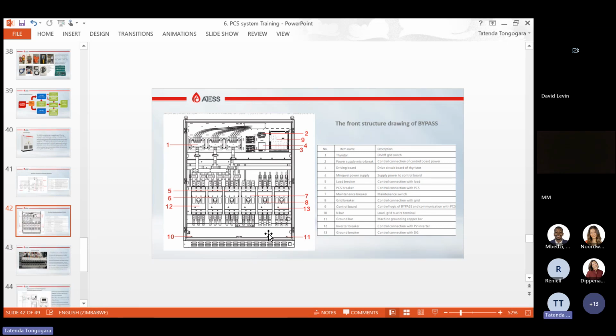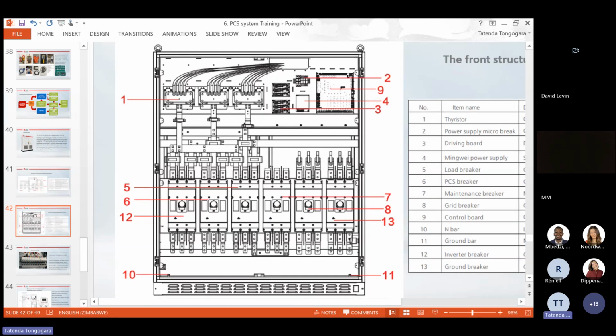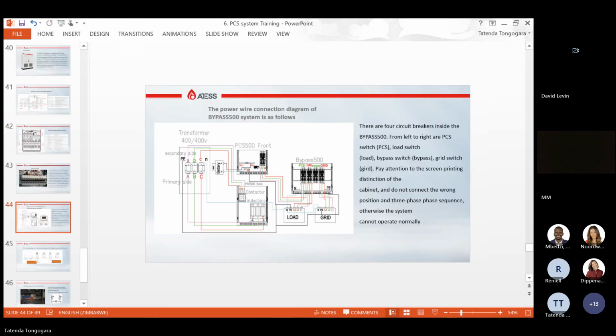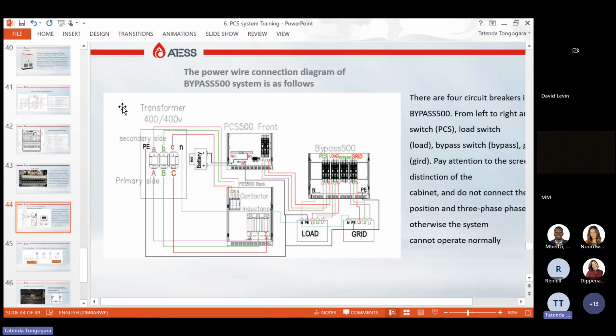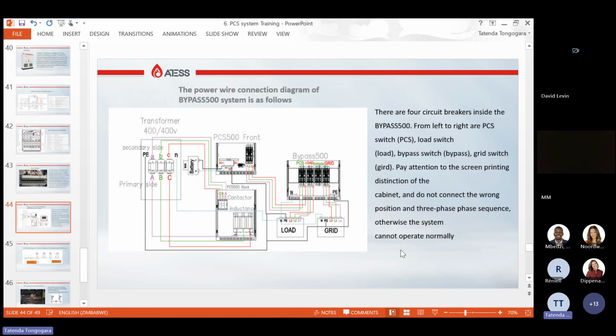So this is the inside structure of our bypass. The PV input, PCS, bypass, your load, grid and generator inputs. So for PCS 500 and above, that is PCS 500, 630, and PCS 1000, you will need an isolation transformer, which is an independent component from the PCS. The PCS 250 has the transformer inside because it's small. But for 500, the transformer is very big. It couldn't fit in the one device.